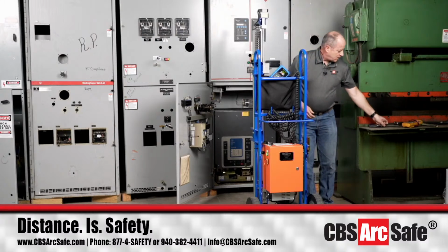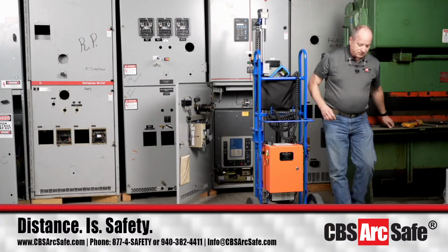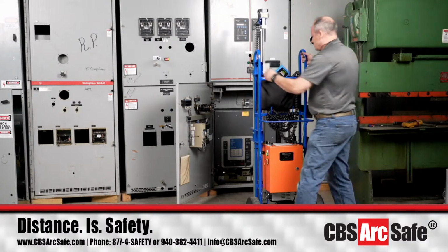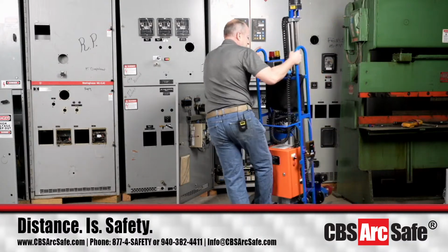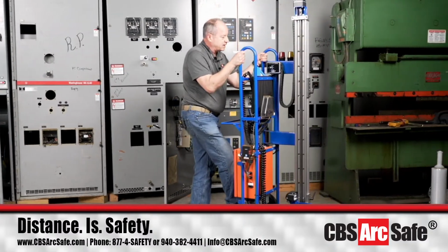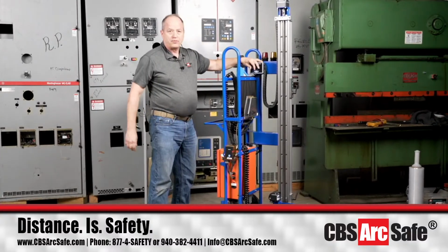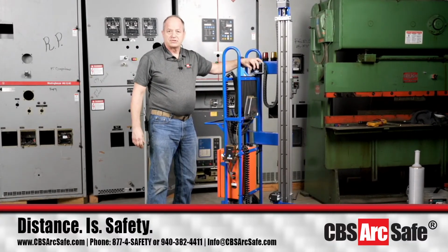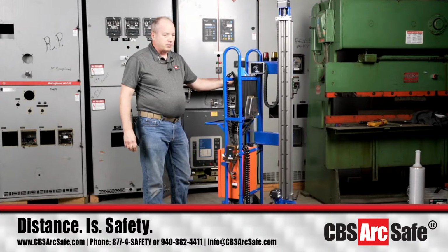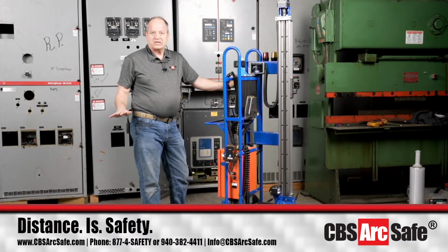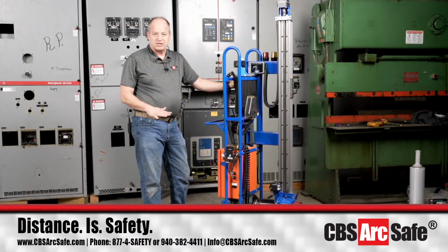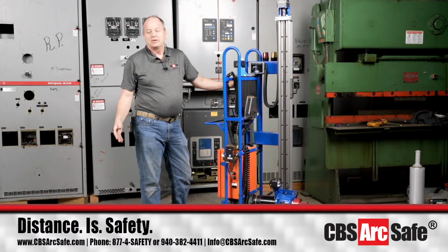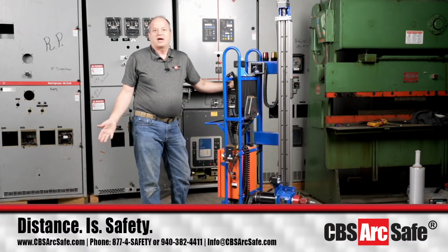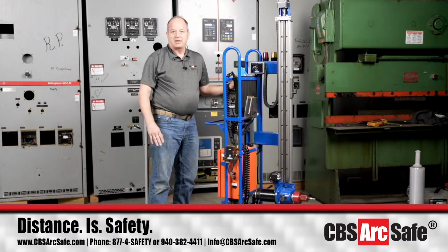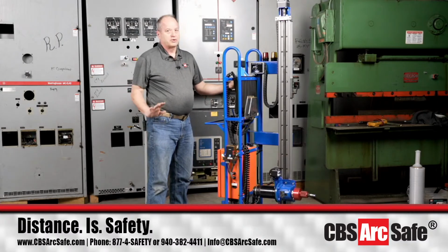I'm going to rotate the unit just slightly so everybody can see it, but this is the power slide feature on the RS-1. We've had some questions about how you are going to raise and lower the motor. This is one of the options. If you have a breaker lineup like just Westinghouse DHPs or Eaton VCP-Ws that are just in the bottom cubicle, you won't need it. But if you've got breakers in top and bottom, 3 or 4 high, you're going to want the power slide.